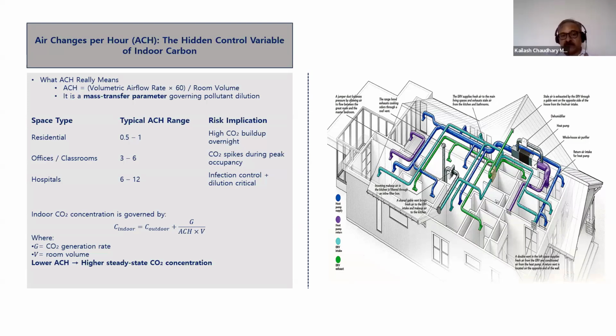From a mass balance perspective, for CO2 accumulation it is the indoor generation minus ventilation. That is the formula for CO2. But for PM 2.5, the accumulation inside your office or any built environment is the outdoor infiltration plus indoor sources minus the filtration or deposition, if it is possible. So if outdoor PM 2.5 is very high, increasing ventilation increases particulate inflow, even if it lowers the CO2. When you take outside air in, the CO2 level will go down, but at the same time you are increasing the particulate matter, which is more dangerous than even CO2. This is a coupled system. One variable cannot be optimized in isolation.